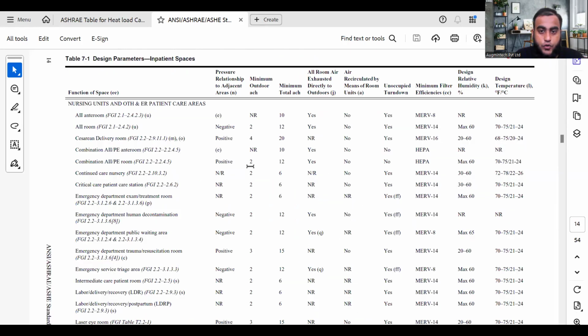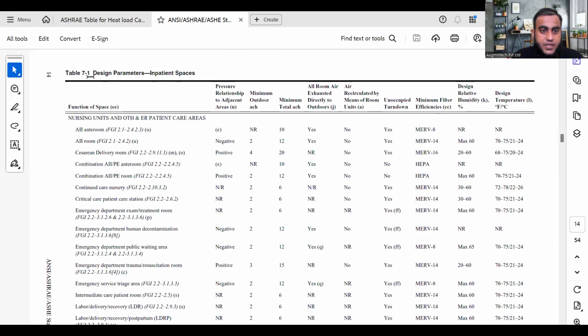See, when you open this page, I don't know, table number 7.1, design parameters in ASHRAE 170. So see here the function of space is given. Can you see? Airborne infection isolation room is given. How much pressure we have to maintain in that room. See, everything is written. Negative pressure always in an isolation room. Generally, we have to maintain negative pressure. Minimum outdoor ACH is what? 2. Minimum total ACH is also given, 12.